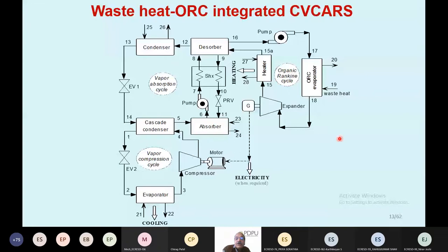As I told you, with the vapor absorption system, you cannot go beyond 5 to 7 degree centigrade. With vapor compression systems, you can achieve lower targets, but the point is, suppose at 35 degree centigrade you reject heat, and you collect heat at minus 10 or minus 20, then a huge amount of compressor work is required.